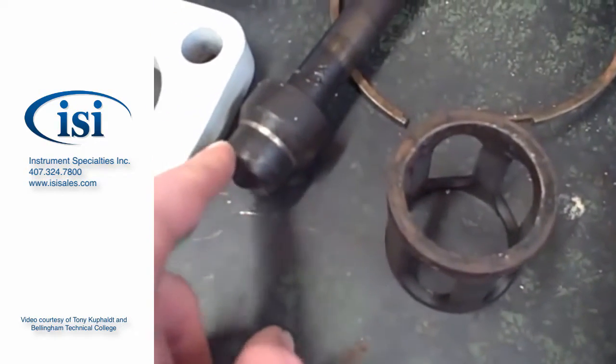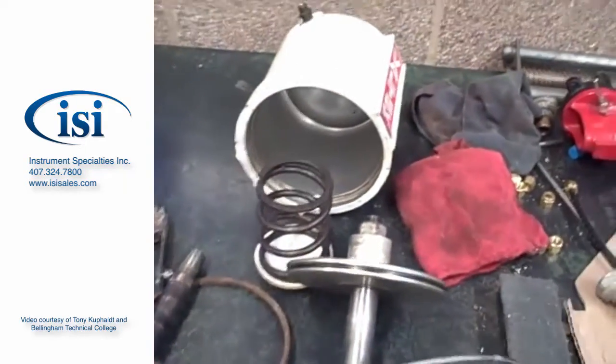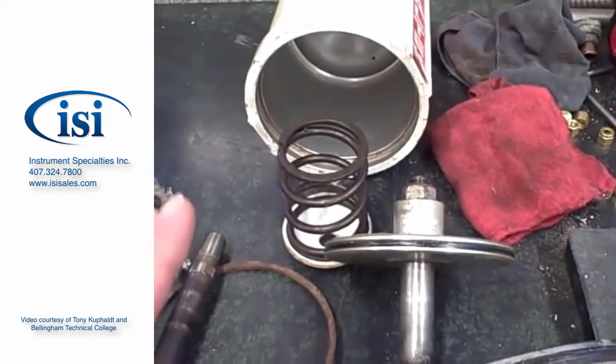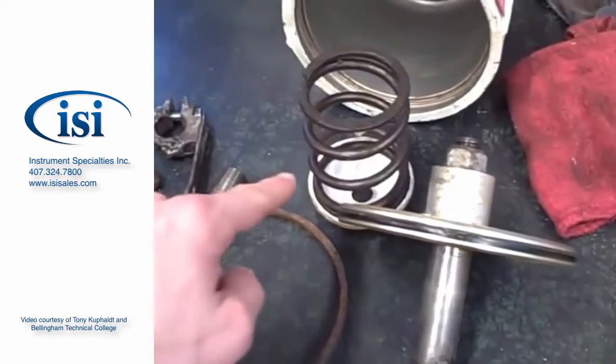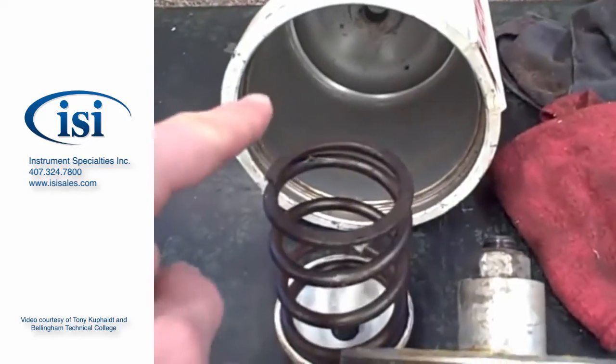The throttling action is done by the end of the plug, not by the walls of the cage. You can see it's a piston actuator instead of a diaphragm. Valtek uses a lot of piston actuators in their valve lineups. We've got the big spring there, the piston with the O-ring seal around the edge, and there's the actual cylinder.